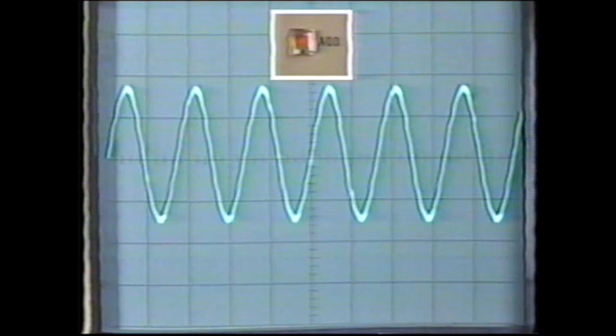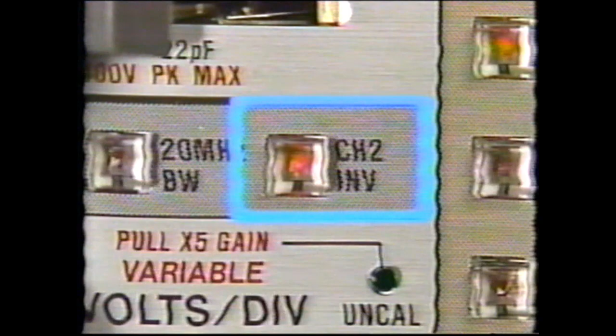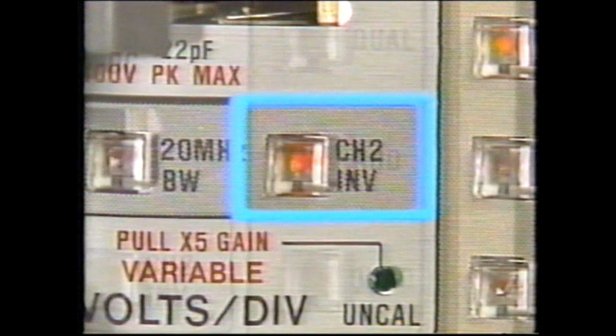In the add mode, input signals from channel 1 and channel 2 are algebraically added together and displayed as one waveform. To subtract input signals, use the channel 2 invert button. Then press the add mode button. This will algebraically subtract the traces. The quad mode will display 4 input signals.